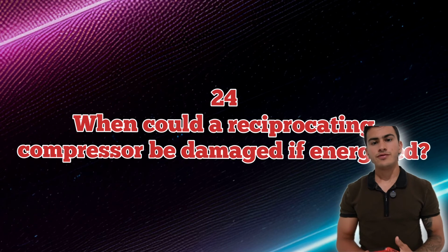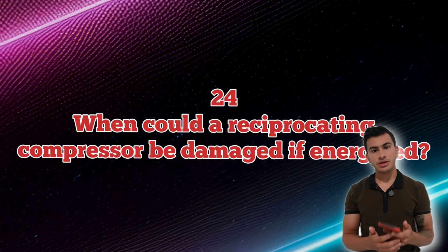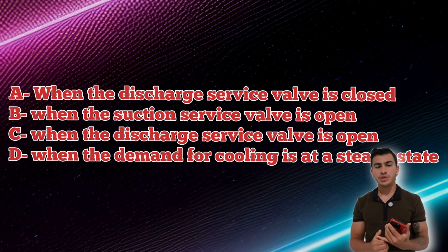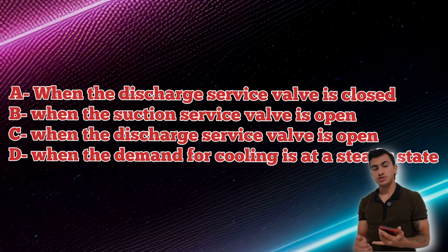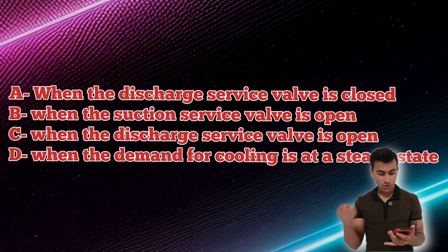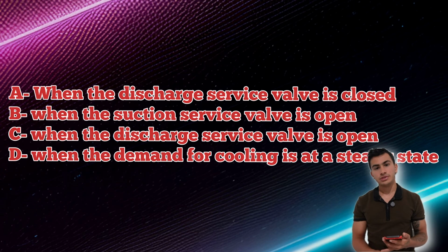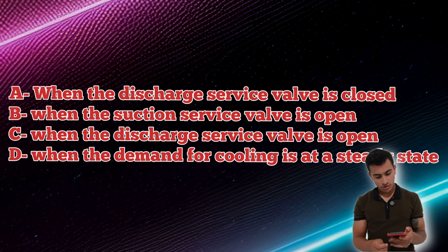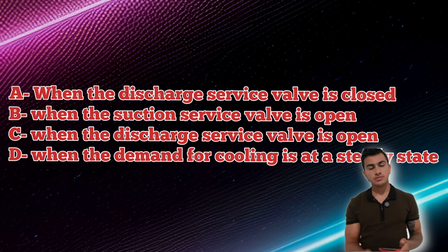When could a reciprocating compressor be damaged if energized? When the suction service valve is open? No. When the discharge service valve is open? No. When the demand for cooling is at a steady state? No. The answer will be when the discharge service valve is closed.